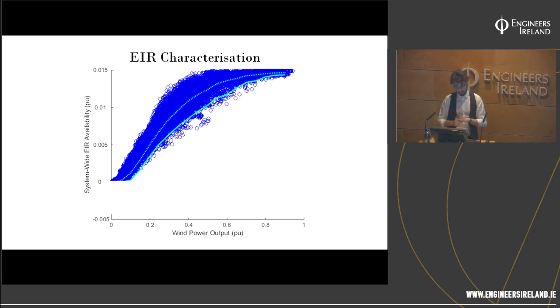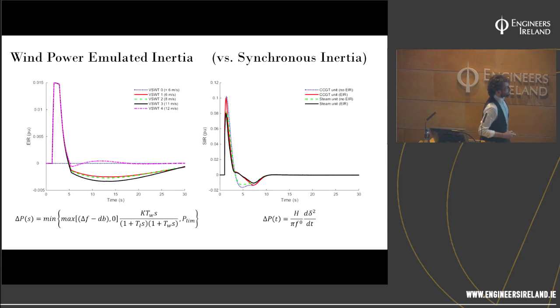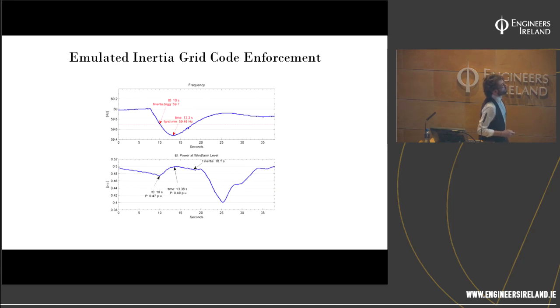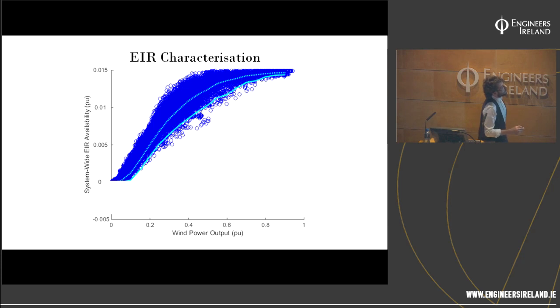So what you're looking at there in front of you is wind turbines online and above that output that's needed for an emulated inertial response. And then that's multiplied by whatever P-lim you give it. So again, these parameters will define the response. Now that's only the magnitude. The shape of the response is inherent. It's not dependent on this number here, which will change from system to system and with how you tune your response.